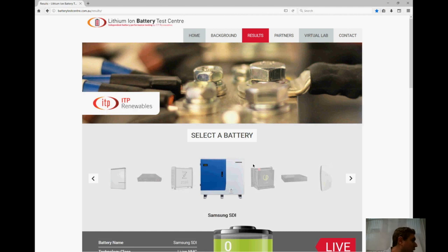So the question is what is the cost of O&M, like a per-unit cost. Pricing ranges, on average, anywhere from maybe 1.5% per year of CapEx, to it could be 5% or 10% per year of CapEx if you're replacing batteries all the time because you extended your depth of discharge range. I've heard of batteries failing in the first 3 months due to excessive degradation because they cycled them with way too high a depth of discharge, way too frequently, and now they have to build into their operating costs the replacement or augmentation of those batteries a lot faster than originally expected.